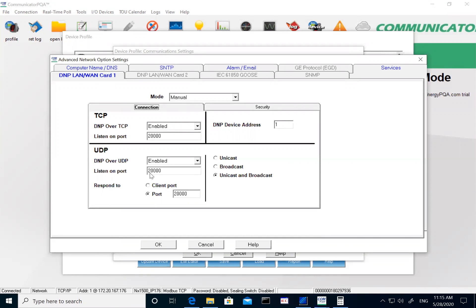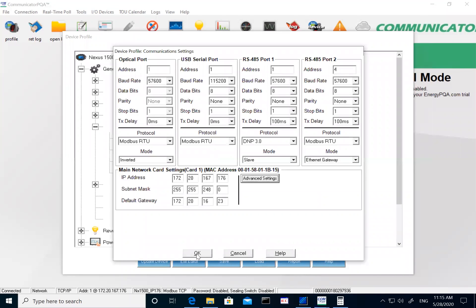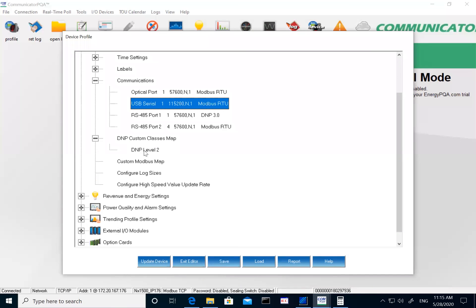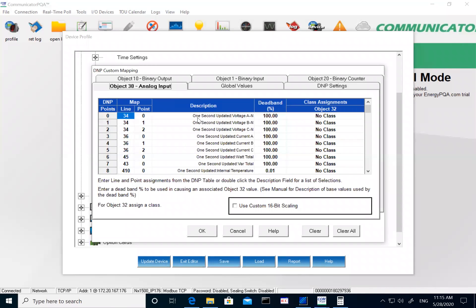Once you are done with IP address settings, click OK. That was the communication part. Now we will go into the detail of setting up the points for the DNP, which is done under DNP Custom Class Map and DNP Level 2. Double-click on this and it will open the detail window. We have them segregated by different tabs for each object. Right now we are looking at object 30 — analog input — where you set up all parameters for real-time polling of your analog signals.